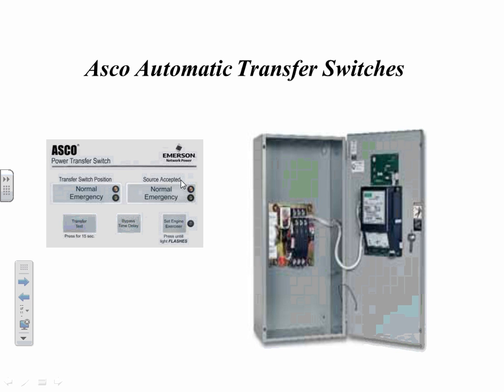I don't know why they say it like this. Other suppliers say source available, but this is source accepted. And in most cases, if all is well, you'll see the normal light lit, and it's typically green. Emergency is typically red on the LEDs. So if we have both sources running, both these will be lit, green and red respectively. Transfer switch position, again, the same colors.